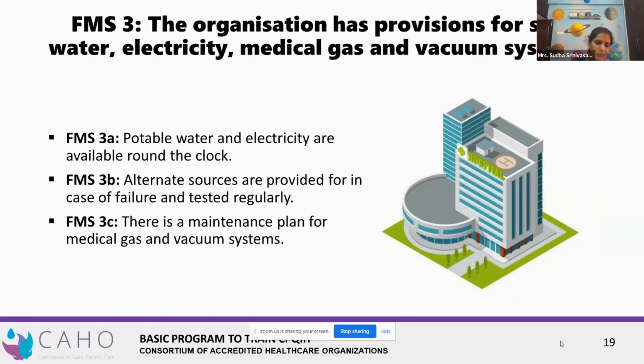A proper calculation must be done on what is the requirement. If it's going to be full occupancy or half occupancy, what on average does our hospital consume in different seasons? That also needs to be considered. At least for 48 hours, potable water availability should be there. For electricity, maybe the hospital was planned 10 years ago with a small setup, and now you are expanding ICU beds or operation theaters. Accordingly, you need to plan for the electrical supply and power requirements.